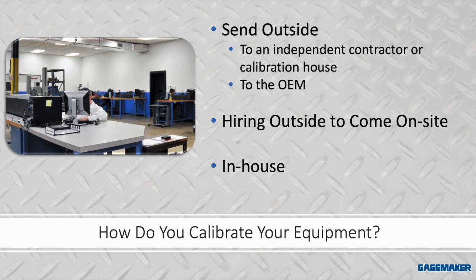Calibration is typically performed one of three ways. The most popular yet most expensive way is to send to an outside service, typically an independent contractor or dedicated calibration house. Another alternative is sending out to the OEM manufacturer of the instrument. Secondary to that is hiring a firm or contractor to come on site to your facility, but that's equally expensive. The best option is creating an in-house calibration system yourself.